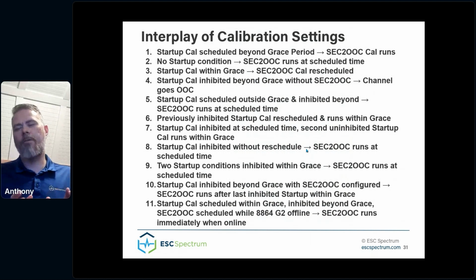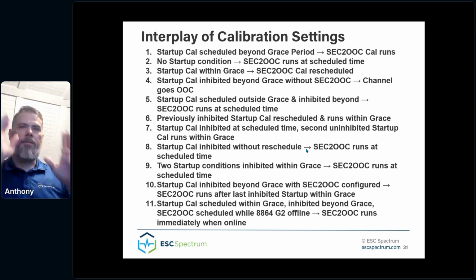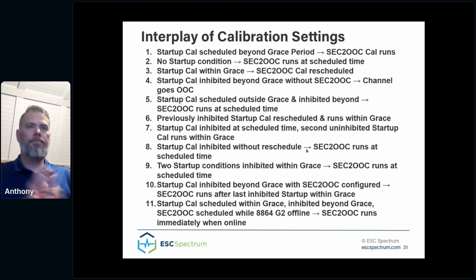And for most configurations, that will always be the case because you're going to be in grace period in your startup anyway. However, if your sector OOC would reach 0 before that startup cal would run, suppose you've got a channel that doesn't have a grace period on it for some reason, then that sector OOC will fire so long as the channel's online, and it will cancel the startup calibration. If you want to explore all the different intricacies of these different data scenarios, they're all in the manual.